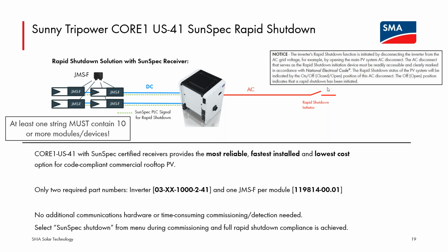For a single inverter, it could be the breaker for the inverter. With multiple inverters, maybe there is a collection panel for the PV system with a main disconnect. That main disconnect could be the initiator, or it could be the whole service disconnect. Anything that will remove utility power from the inverter's terminals can act as that rapid shutdown initiator.